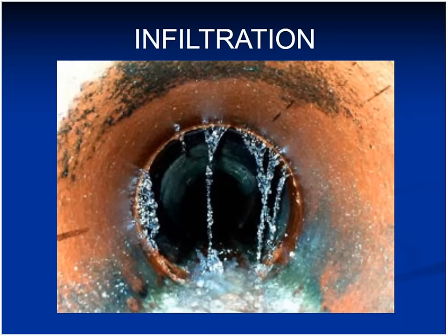Two things are causing that issue, even if you have a separated sewer system, what we call I&I. First I is infiltration. Inflow is a result of poor condition of your collection system. Cracked pipes, broken pipes, poorly installed pipes, bad joints. Rainwater comes, percolates through the ground as you want it to. But then it sees this big 36-inch pipe that's just open space. It's a whole lot easier to go in there than to fight its way through the gravel. And it goes. And that's just extra flow going to the plant to make life harder.